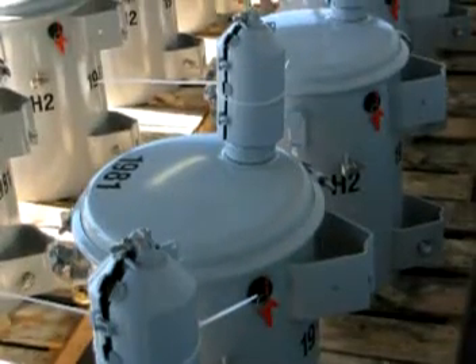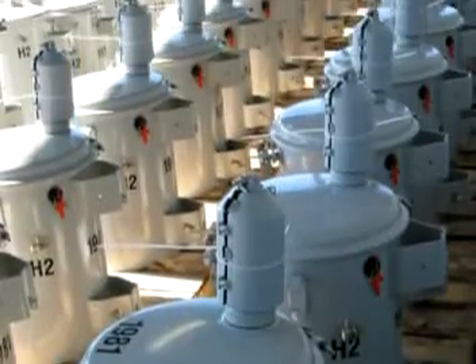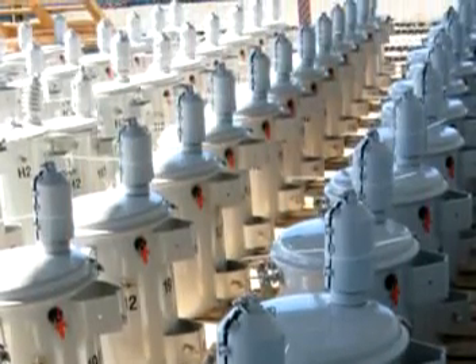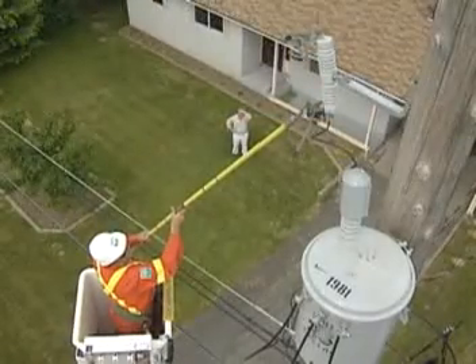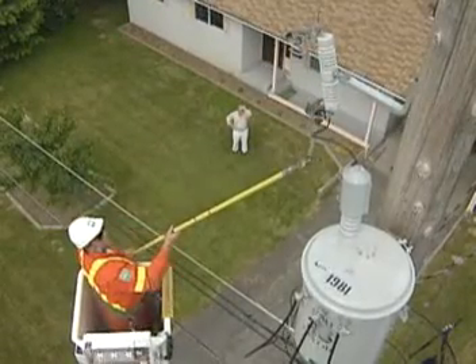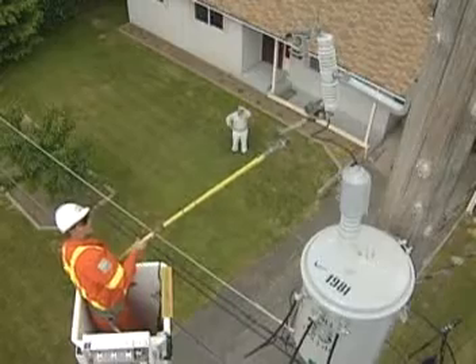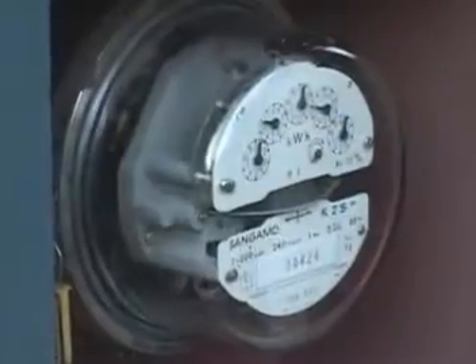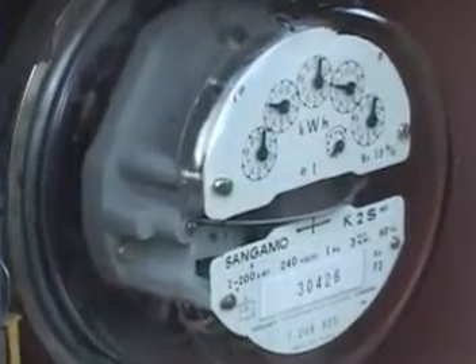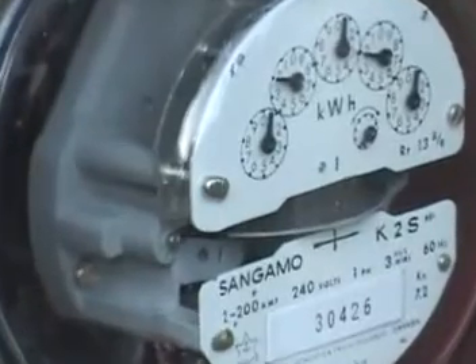IFDs are inexpensive to purchase and easy to retrofit in transformers that are returned for repair. From a customer service perspective, a utility that uses IFDs can restore power faster. And from a network reliability perspective, restoring power quickly reduces the utility's System Average Interruption Duration Index, which results in increased quality of service and additional cost savings.